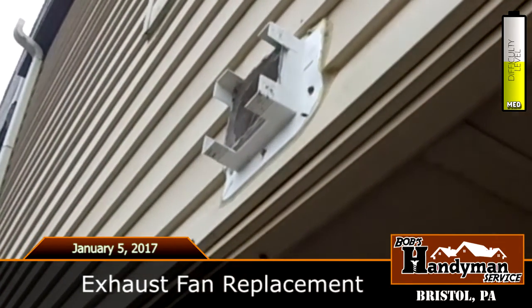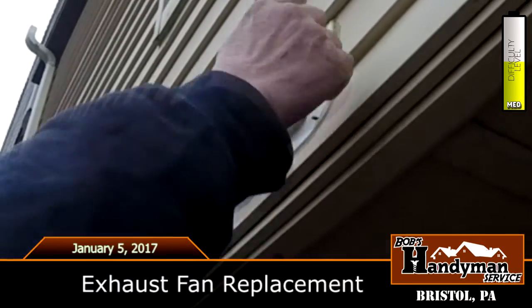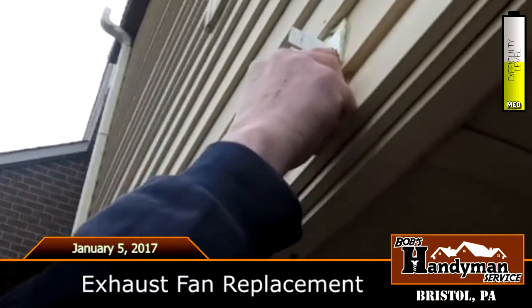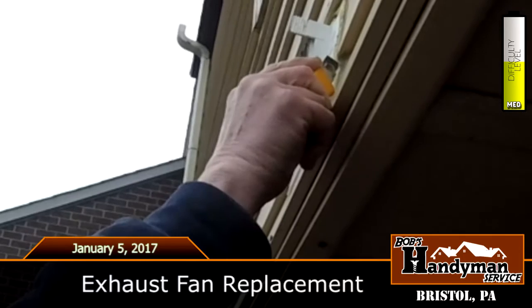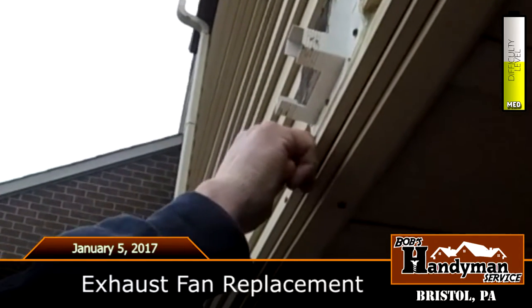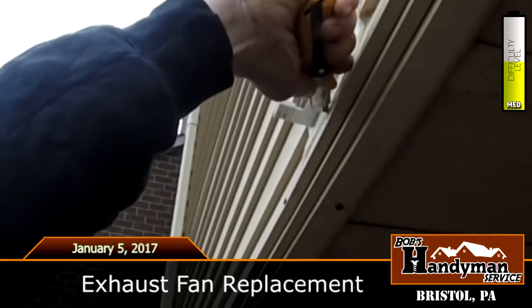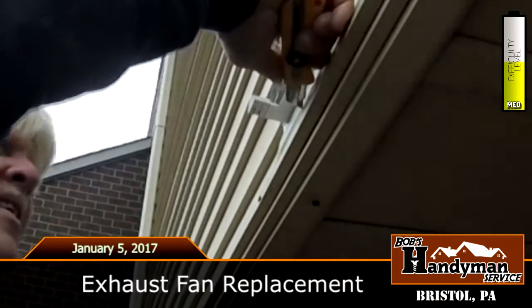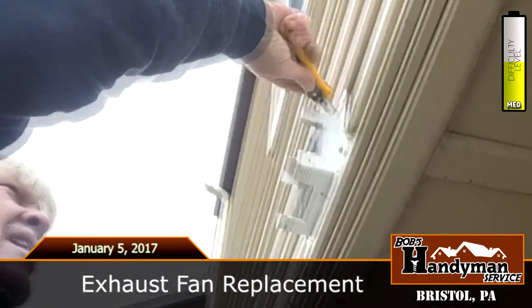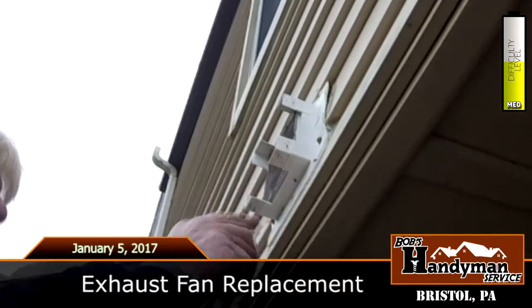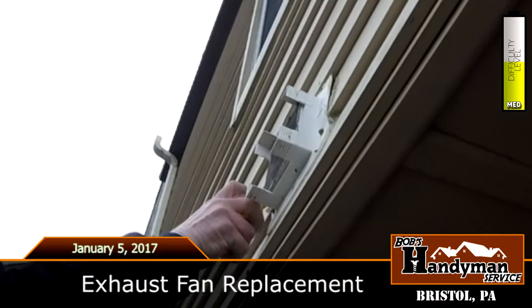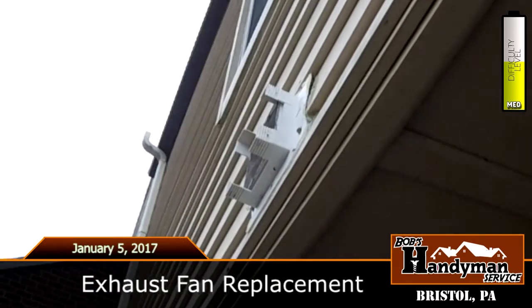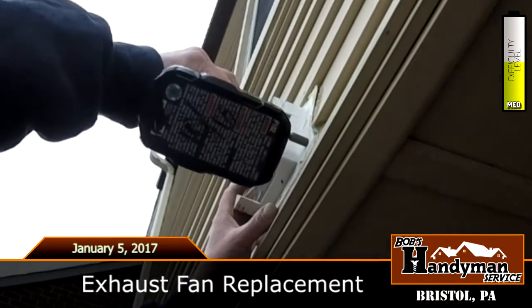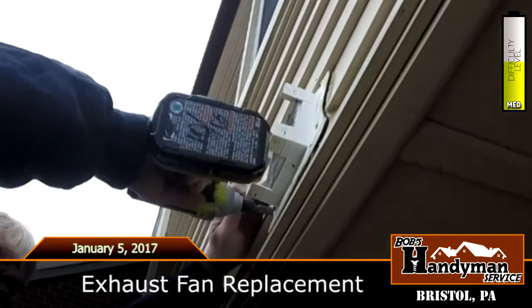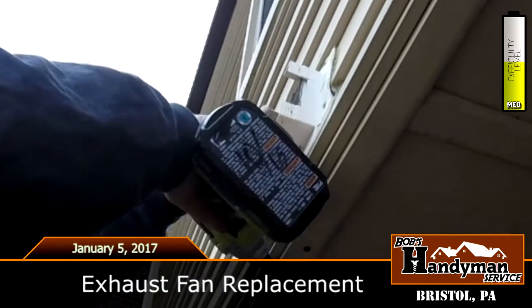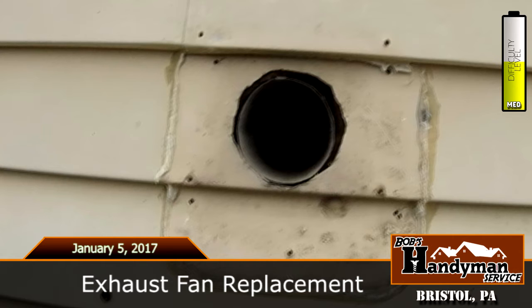My associate is removing the cover so that he can access the edges of this cover plate. He's running a razor knife around the edges, separating the caulk from the cover plate. Be careful when doing this as to not damage the vinyl siding in any way. Once the silicone is all cut away from the side of the unit, go ahead and take the screws out, removing the faceplate and exposing the exhaust pipe where it comes through the exterior wall of the home.